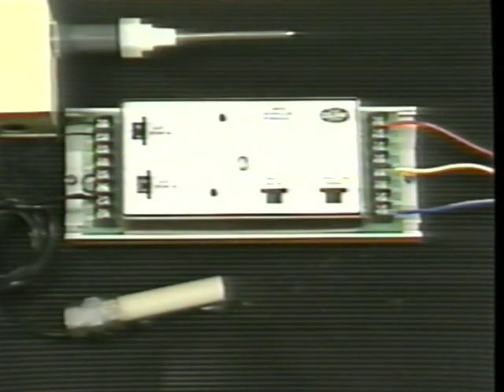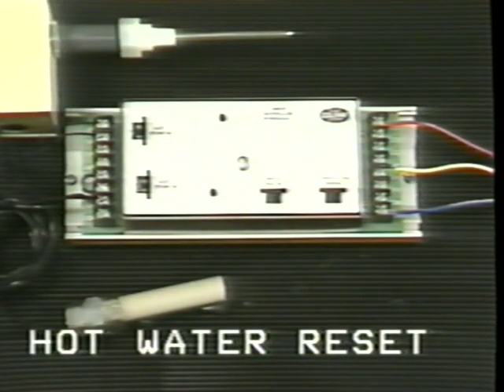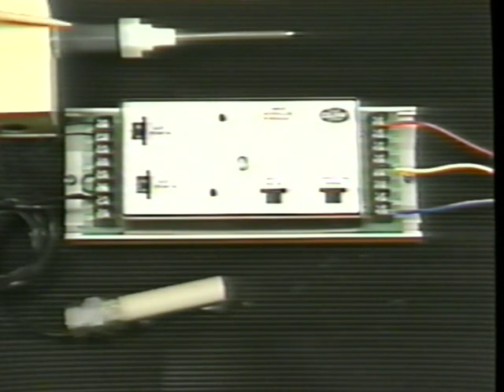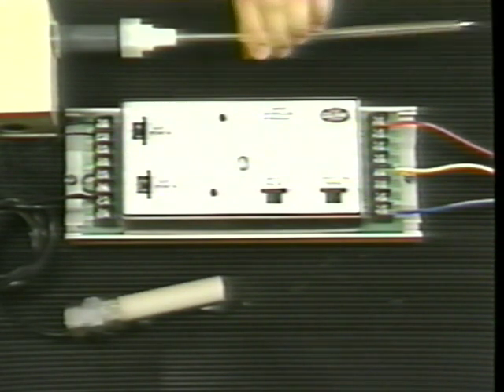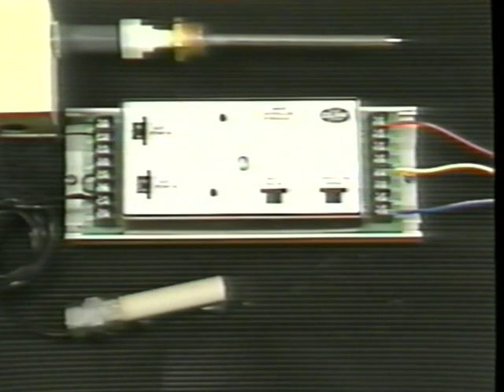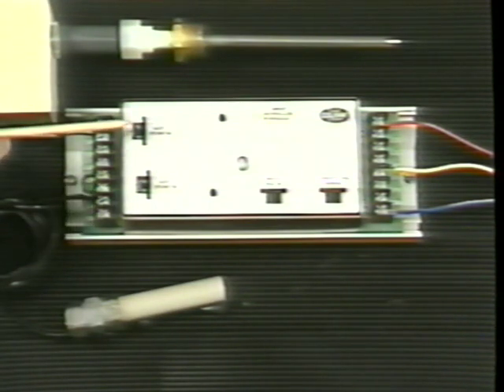One of the most common applications for the CP8102 is outdoor reset of hot water. The demonstration board shows a sensor, the TS8201, which would be used to measure the hot water temperature, usually in a liquid line. When used in that manner, a well is necessary. Since the hot water temperature is our control variable, this sensor must be wired to the ISA terminals of the controller. Outdoor air, our resetting medium, is measured by the TS8501. The outside air temperature, as represented by the signal input at ISB, serves to reset the hot water set point.